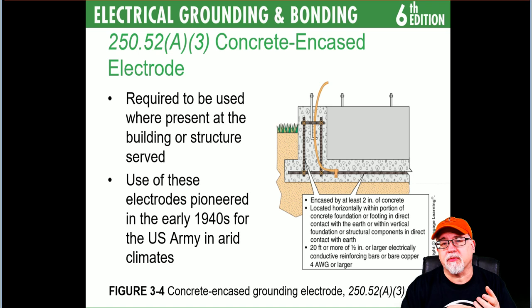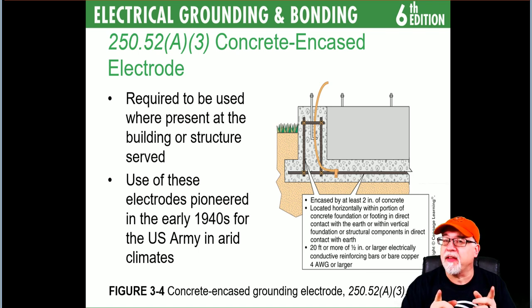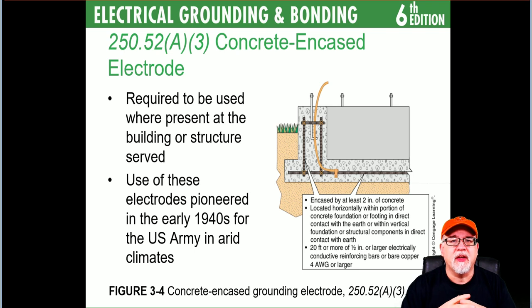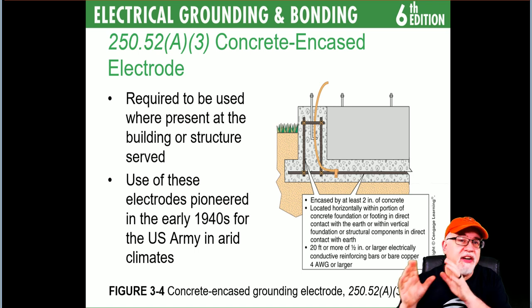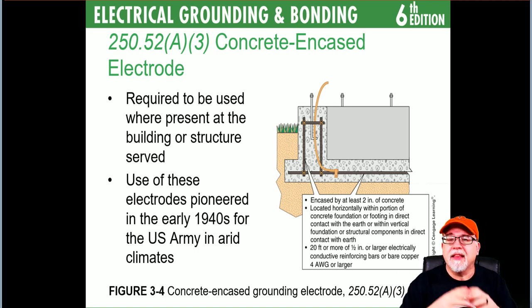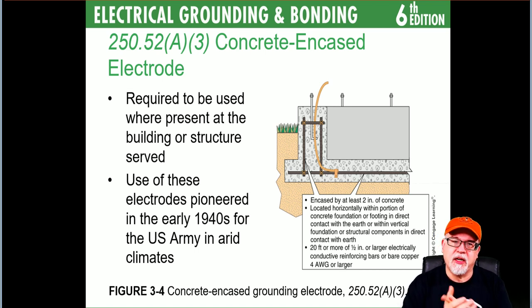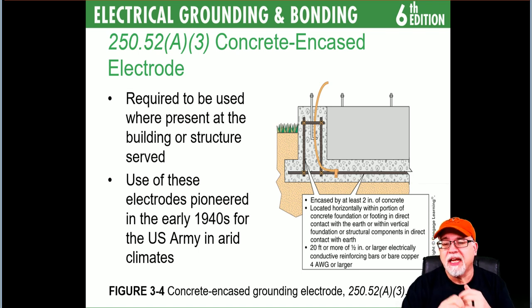250.52(A)(3) — concrete encased electrodes — are required to be used where present. They are typically present in all installations where you have a concrete footer or foundation in direct contact with the earth. If there's a vapor barrier making the foundation not in direct contact with earth, then it is not a concrete encased electrode — it has to be in direct contact.